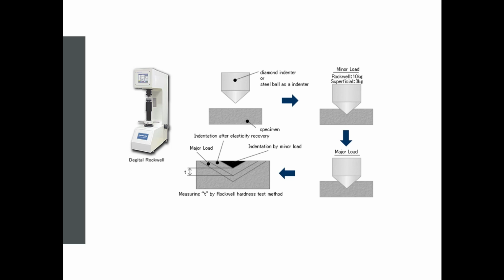So, this is the figure. This is the automatic machine which is used for measuring the hardness. Here, having the same construction as Brinell, this is an elevating screw, this is a hand wheel, and this is a frame. Here you can adjust the load, and here you can select the scale. There will be a scale mark over this frame. This is a plate which will denote the scale and its application.